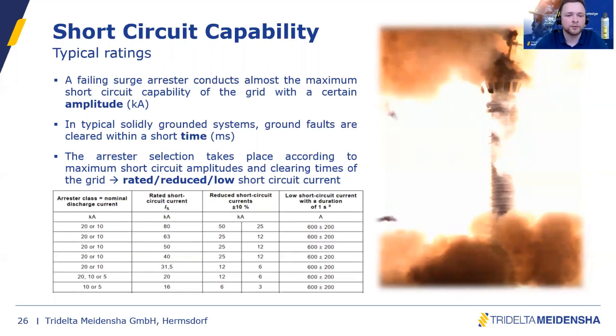You can see it here in this table. For example, a very typical value for 20 or 10 kA discharge class or station class surge arrestors is 63 kA rated short circuit current. Sometimes you see 65 kA, which has been an older specification. So if 65 kA is on the test report, 63 kA is also covered. Of course, it's a little bit higher. And then we also have to test 25 and 12 kA. And we also have to test 600 amps with a total duration of 1 second. So that's very long for a current like this. It's also challenging to withstand currents like this.